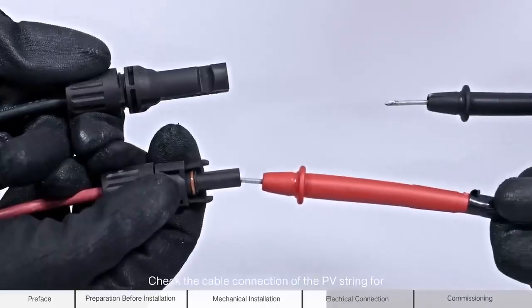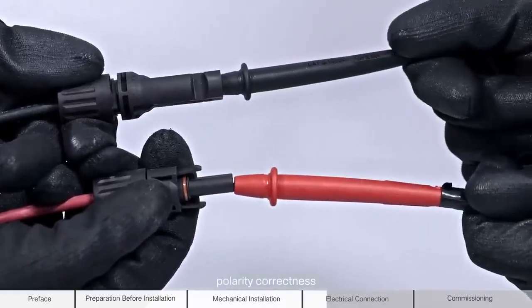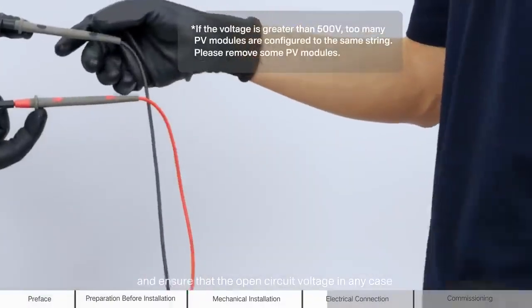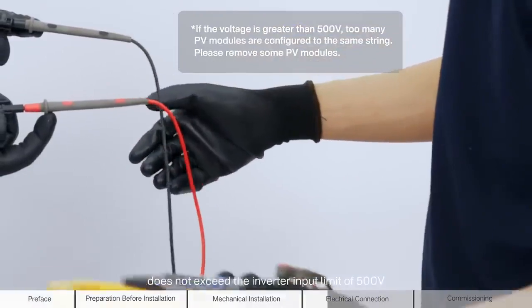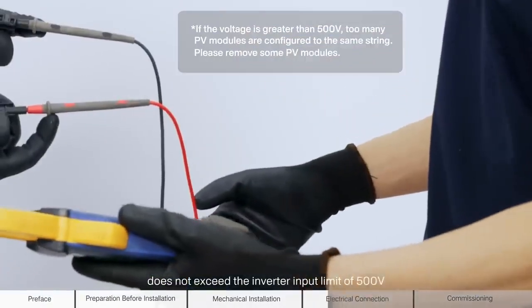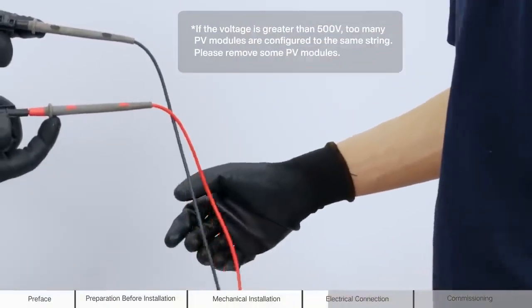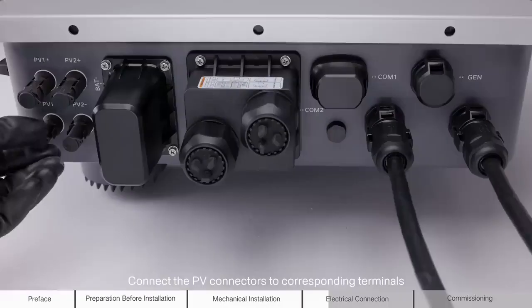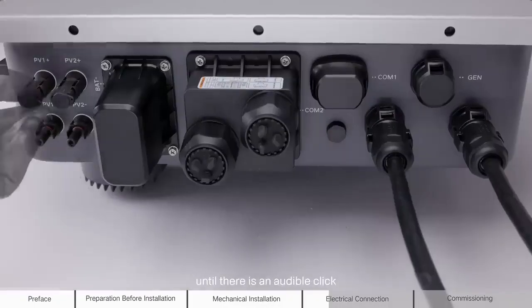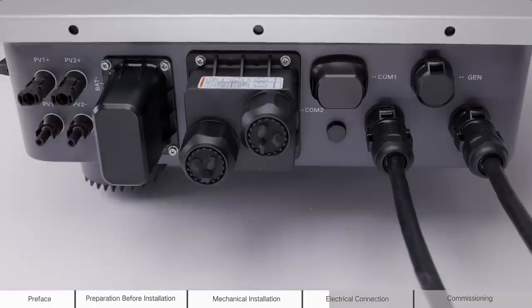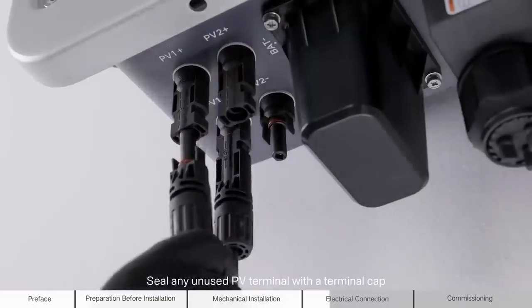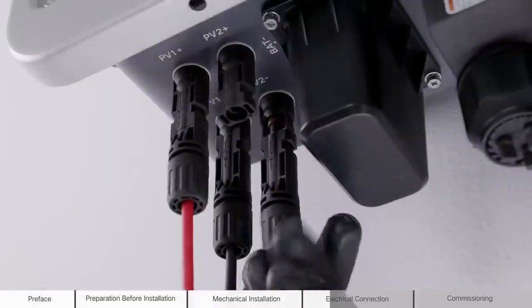Check the cable connection of the PV string for polarity correctness and ensure that the open circuit voltage in any case does not exceed the inverter input limit of 500 volts. Connect the PV connectors to corresponding terminals until there is an audible click. Seal any unused PV terminal with a terminal cap.